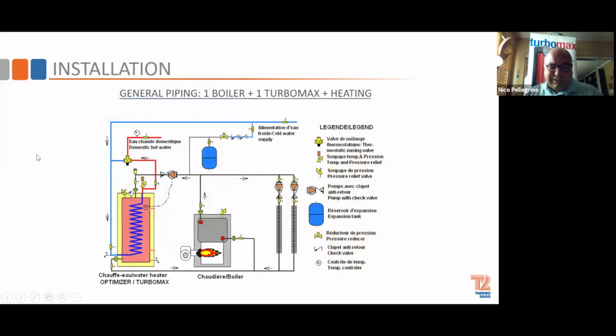So basically, a standard, very basic system: domestic production and space heating, one boiler, nothing fancy. The thing is, we put the boiler water in at the top of the tank, and the domestic goes in at the bottom of the tank. So we actually reverse flow. So that gives you a good buffering system and a good thermal mass of boiler water in the Turbomax to help with the runtime on the boiler.